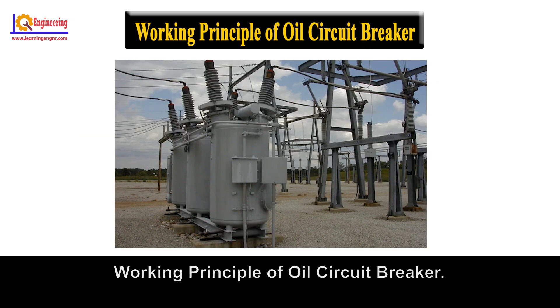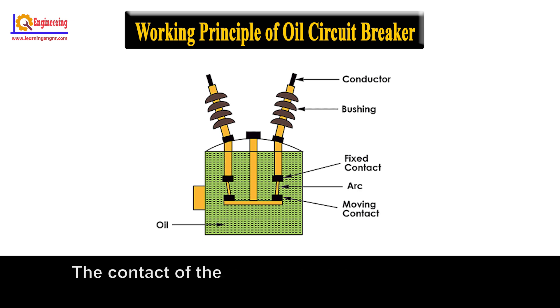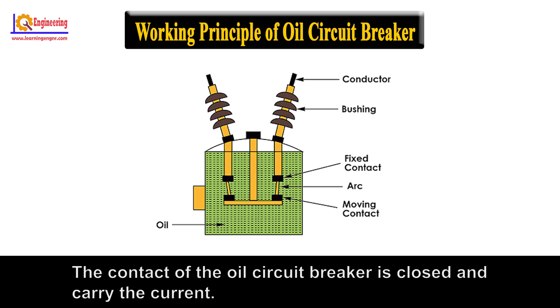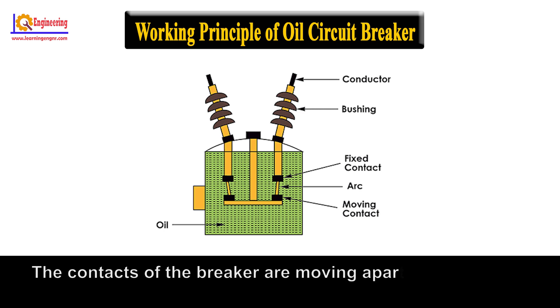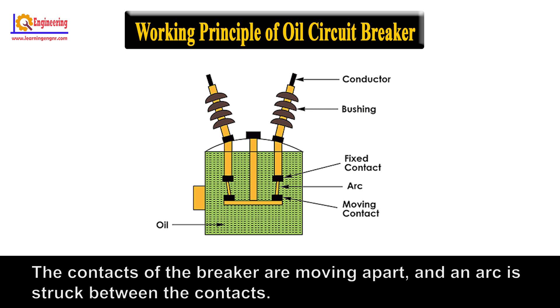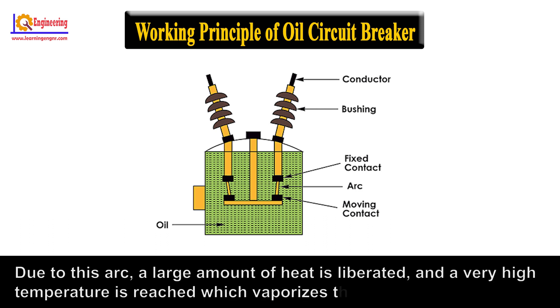Working Principle of Oil Circuit Breaker: During normal operating conditions, the contacts of the oil circuit breaker are closed and carry current. When a fault occurs in the system, the contacts of the breaker move apart and an arc is struck between the contacts. Due to this arc, a large amount of heat is liberated, and a very high temperature is reached which vaporizes the surrounding oil into gas.